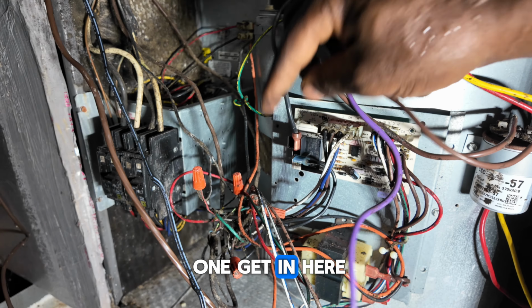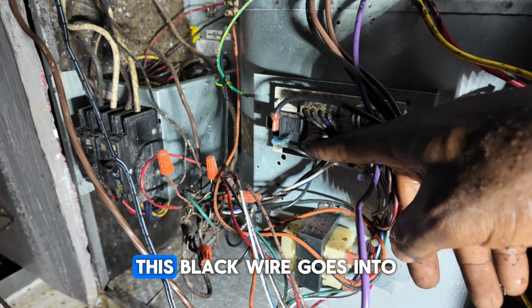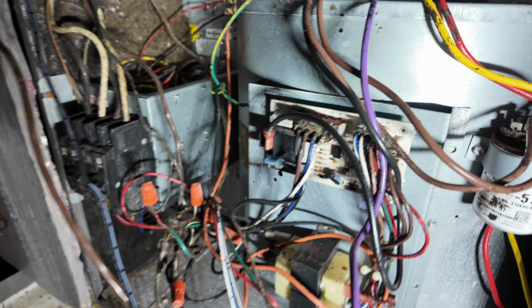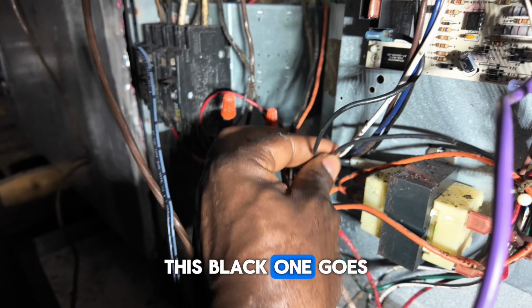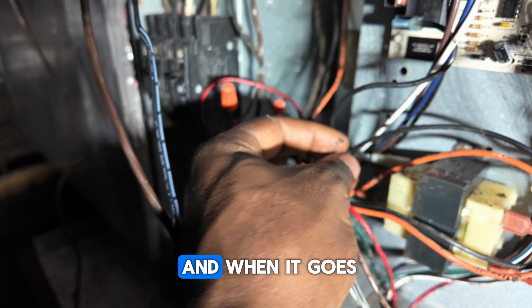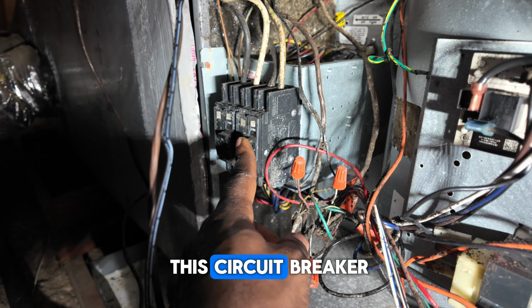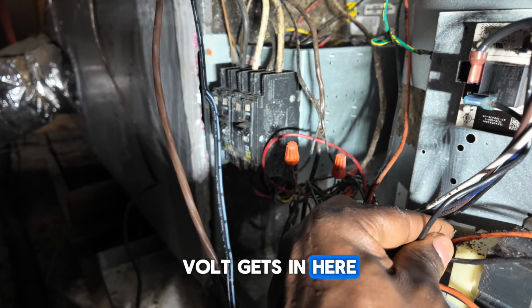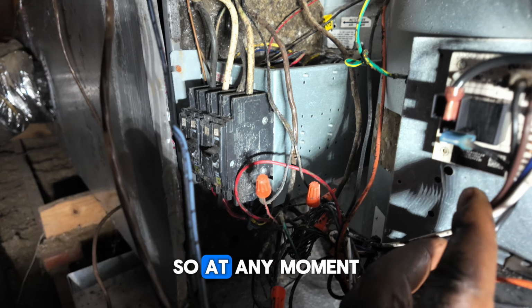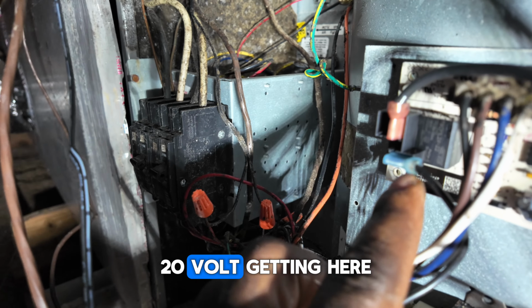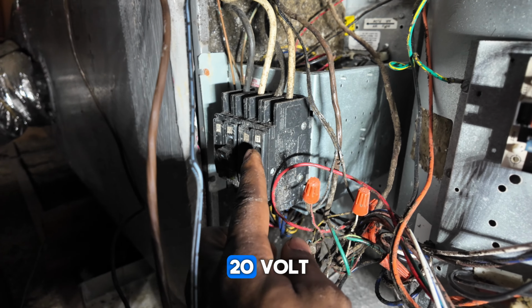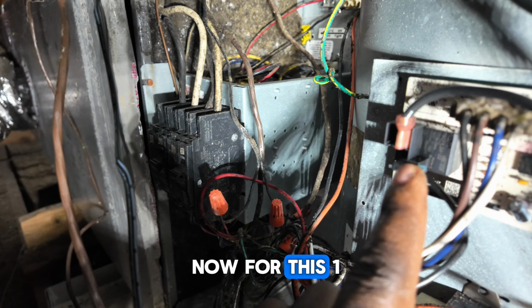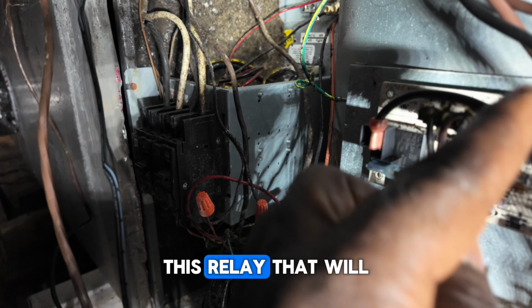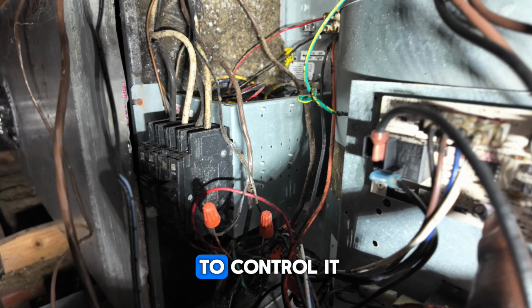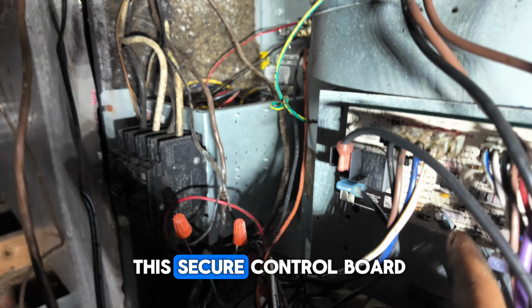Now, you see this one get in here, and you also see another black wire from here. This black wire goes into this terminal. Look at it. This black one goes into this transformer terminal, and from this terminal it goes into this circuit breaker. That means 120 volt gets in here, and then they split it, pick it up, and bring it here. So at any moment, as long as this breaker is on, there will be 120 volt getting here. It's like you pick 120 volt from one of these terminals and bring it here. Now for this 120 volt to run through this relay and go into the fan, the control board needs to control it. So this is like a switch controlled by this control board.